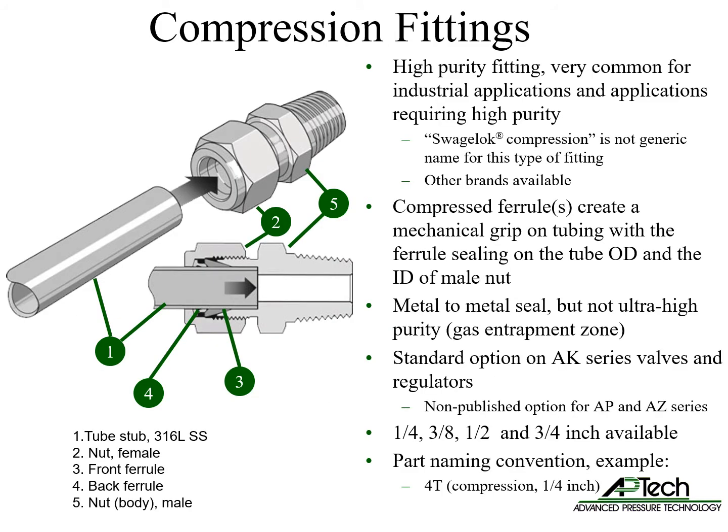Compression fittings are high purity fittings, one step below ultra high purity face seal fittings. They are very common for industrial and other applications requiring high purity. Brands include Swagelok and others — many customers incorrectly refer to compression fittings generically as Swagelok fittings, but there are many brands. The compression fitting mates with a tube stub. There are single and double ferrule methods. Two ferrules are compressed to create a mechanical grip on the tubing, which seals with the male nut inner dimension, forming a metal-to-metal seal, but it is not considered ultra high purity due to its gas entrapment zones.